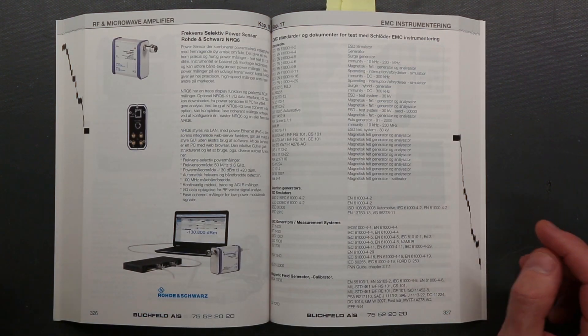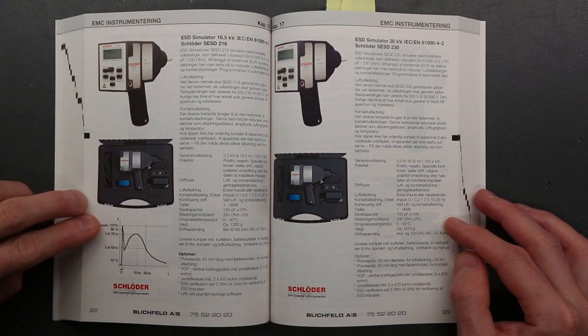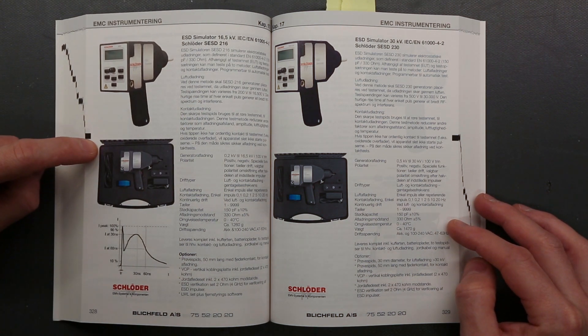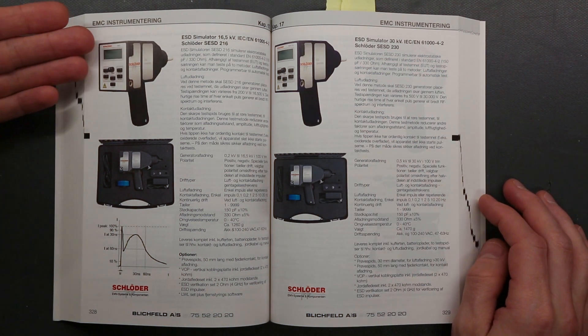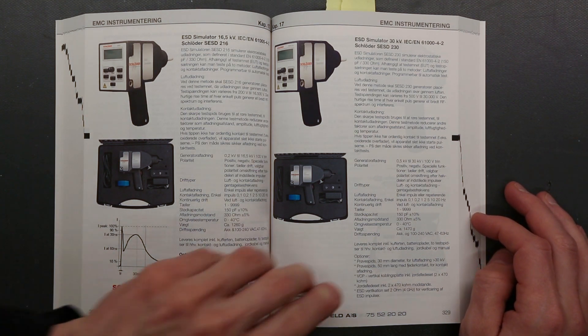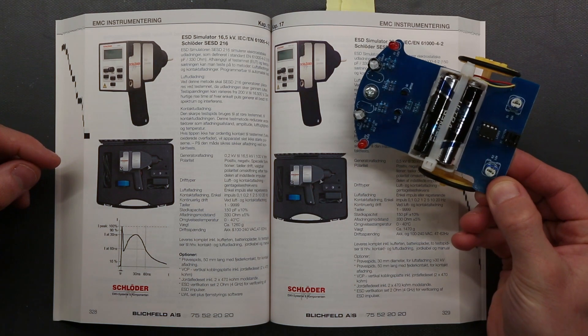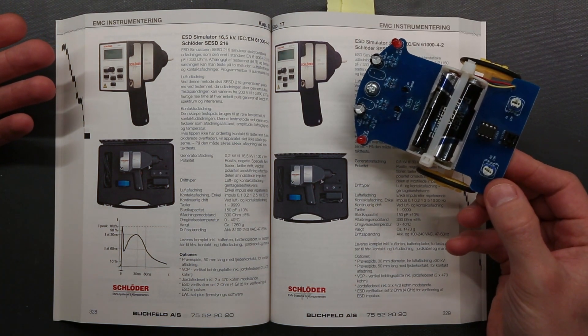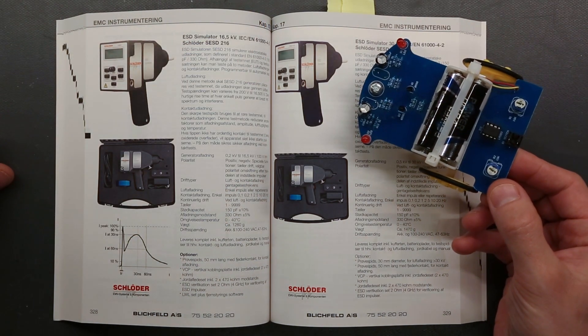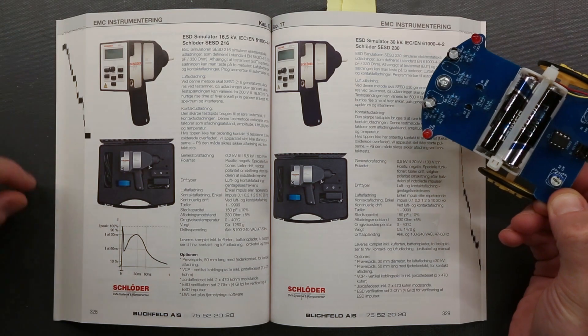Now we are into the EMC section with general EMC test sets. Here we have some ESD simulators that can inject 16.5kV and 30kV — all made into a handheld unit from Schlöder. Interesting that you can test your circuit — say you design a small circuit like a robot car and want to test its EMC compatibility. You just take your apparatus, inject some high voltage transients into the circuit, and see if it survives. If it does not, you don't have enough protection against what you are injecting.